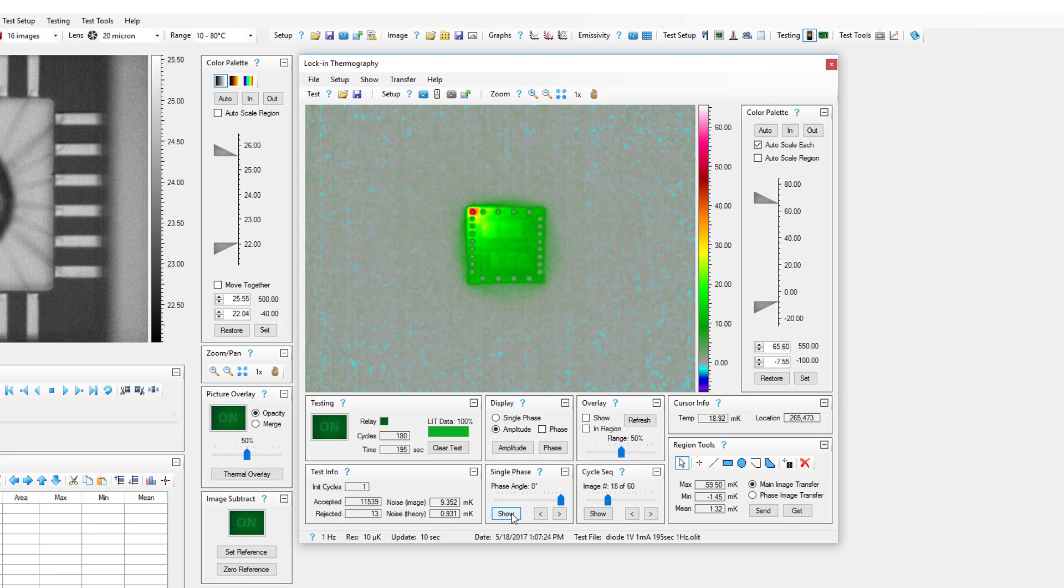Single phase images display temperature increases at a specific time in the cycle. They can also identify areas that heat up at different times within the cycle, providing an approximate correlation with defect depth. Single phase images typically produce the highest XY spatial resolution of all lock-in images.